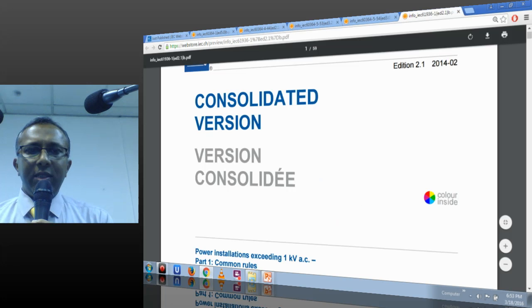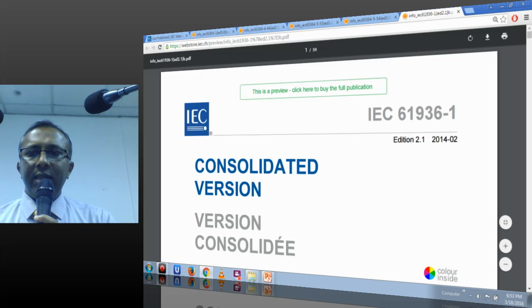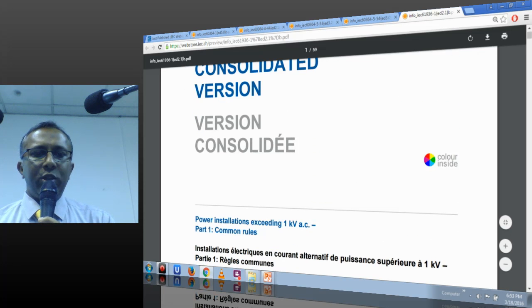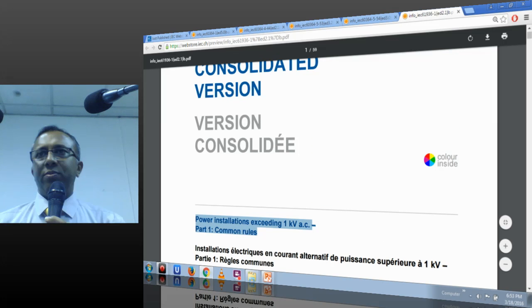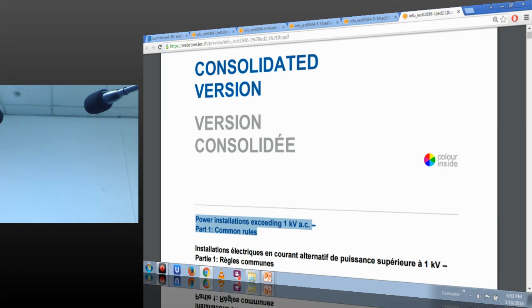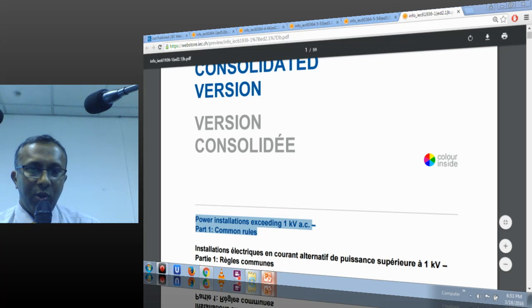Another question is, see, 61936 talks about power installations exceeding 1 kV, common rules. So this standard gives an indication whether the neutral and transformer body need to be separate or connected together. If it is connected together, what kind of LV network you have to have, what kind of protection devices you need to have. All these conditions are explained in the standard, and the standard also explains under what condition you can do a connection of this.